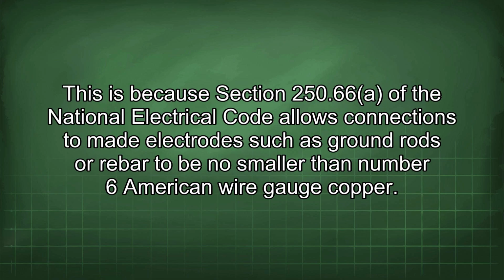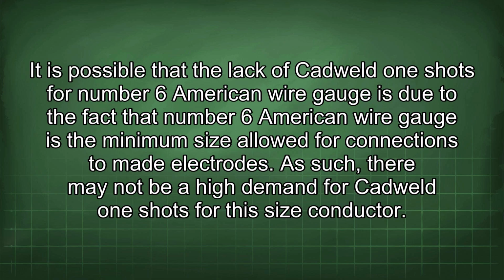This is because section 250.66 of the National Electrical Code allows connections to made electrodes such as ground rods or rebar to be no smaller than number 6 American wire gauge copper. It is possible that the lack of Cadweld one shots for number 6 American wire gauge is due to the fact that number 6 American wire gauge is the minimum size allowed for connections to made electrodes. As such, there may not be a high demand for Cadweld one shots for this size conductor.